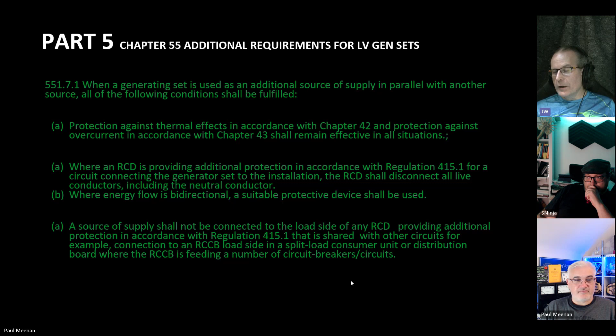I remember talking to Mr. Scum about this. You remember when we were at LX and we had the stand and we had the wall of wants? Yes. Yeah. He drew this out and he did the AFDD with us, and then he did this and he said about 415.1, RCD additional protection, you shouldn't put them with an inverter on the load side because they will not achieve disconnection within 40 milliseconds because the inverter will not disconnect within that time frame. He said it then. And that was going back to the feed-in tariff days.